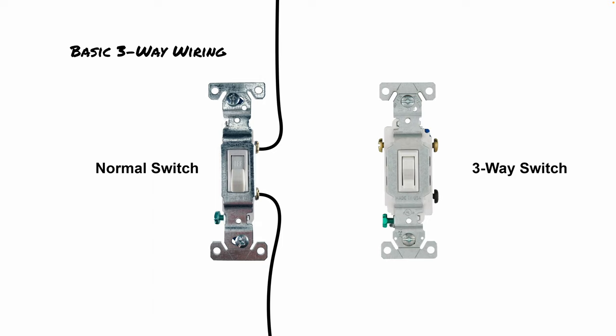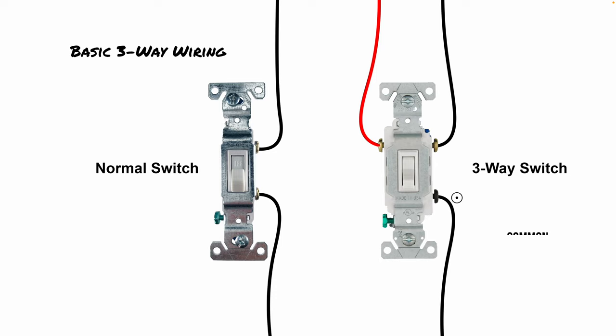On a three-way switch, you've got the hot wire coming into the black terminal typically, and then you've got two brass terminals that are used for the traveler wires. The traveler wires are what lets the three-way switches work independently to control the lights and make sure they turn on and off. We'll talk more about those in a second.